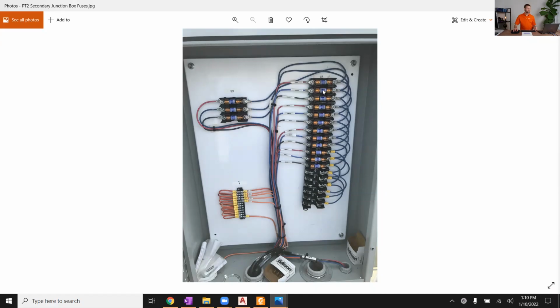Good job, Kevin. So if you have a short circuit where the phase to the neutral gets shorted together somewhere down line of those fuses, again, you could have an arc, you could have a high current situation. You want this fuse to open circuit to clear that short circuit fault on the secondary system. So we have these PTs, fuses to protect against short circuits. An open circuited PT is fine. That doesn't cause any harm. You got a potential difference you can measure across it with your voltmeter, just fine. But a short circuited PT is not a good thing to have. And so we use fuses to protect that.